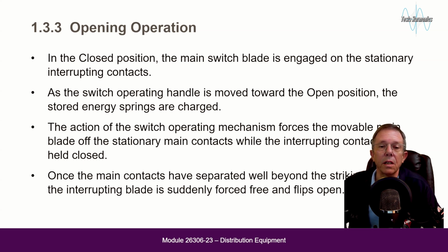Opening operation. In the closed position, the main switch blade is engaged on the stationary interrupting contacts. As the switch operating handle is moved towards the open position, the stored energy springs are charged.